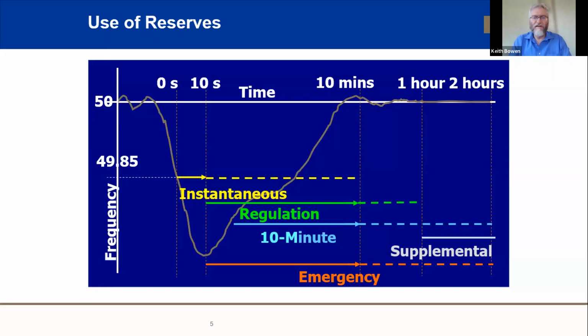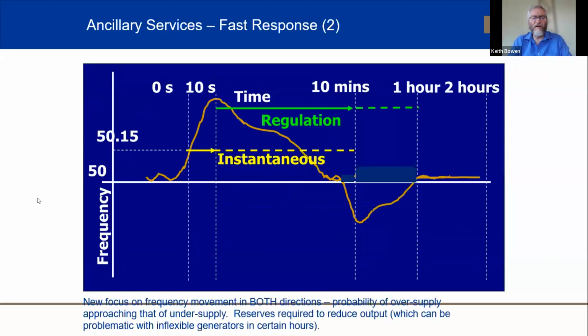I hope that provides some technical background on what happens with these different types of reserves. Interestingly, one thing becoming more of an issue for us, relatively new, is the risk on the upside. We've traditionally worried about the drop in frequency, but now with renewables you often have too much generation, so your frequency climbs. That can happen when the wind is there when you didn't expect it, and you can't back off enough generators, so you start seeing frequency increase.